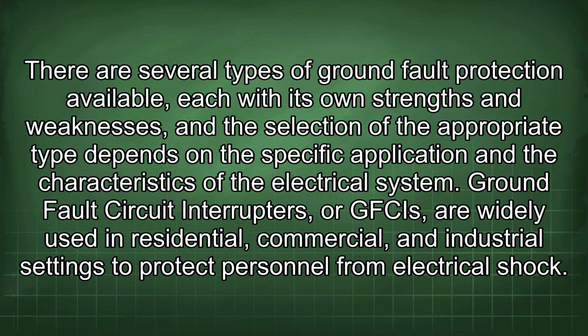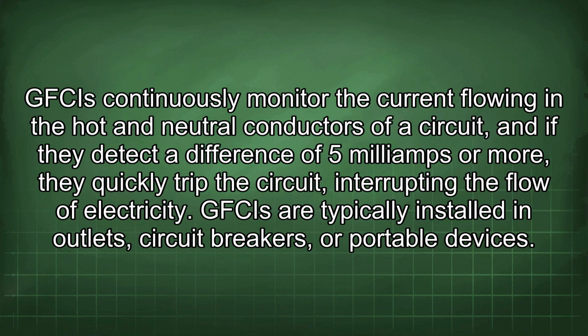Ground fault circuit interrupters, or GFCIs, are widely used in residential, commercial, and industrial settings to protect personnel from electrical shock. GFCIs continuously monitor the current flowing in the hot and neutral conductors of a circuit, and if they detect a difference of 5 mA or more, they quickly trip the circuit, interrupting the flow of electricity. GFCIs are typically installed in outlets, circuit breakers, or portable devices.